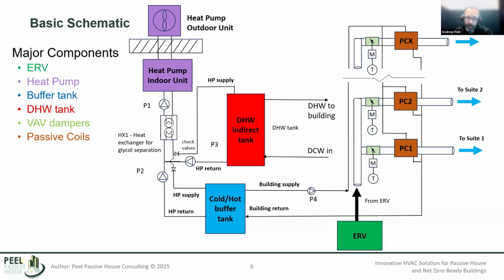Especially for small multifamily buildings, I think they work well with a central ERV, which is one way we could reduce costs—having a shared ERV across four suites delivering fresh air. At the same time, we'd have a passive coil, not a fan coil unit but just a passive coil that air flows through, fed with either heated or chilled water. That heats or chills the fresh air coming into each suite. So although it's a centralized system, we'd still have individual control of heating and cooling in each suite through its own passive coil.